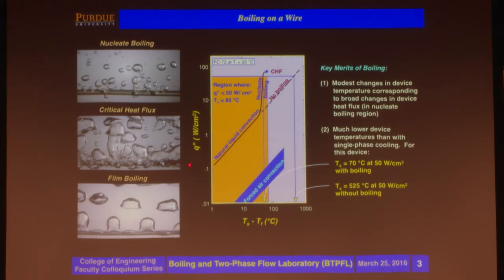We have a plot of heat flux versus temperature difference between the surface and the coolant. The orange area is where you expect operation to take place. You want to dissipate heat fluxes up to 50 watts per square centimeter, but the device surface cannot exceed 85 degrees centigrade. With forced air convection, you're never going to be able to do it. With natural liquid convection, without phase change, again you find that by the time you hit the 50 watts, you're going to reach 500 degrees.